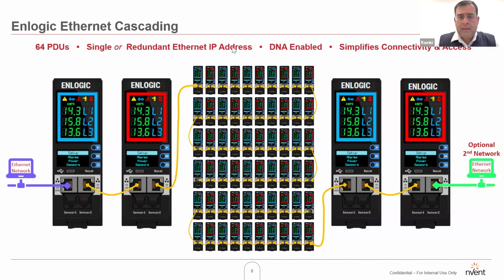Not only that, but having two Ethernet ports on the PDU itself gives you the ability to connect a redundant network on the other port. This is a very important feature that differentiates the Enlogic PDU from what you would typically call a daisy chain configuration.